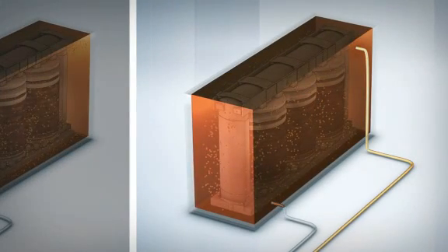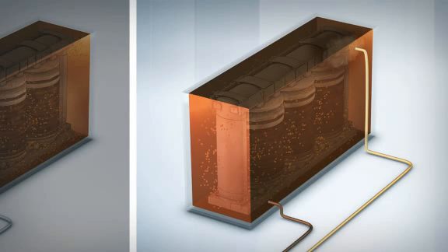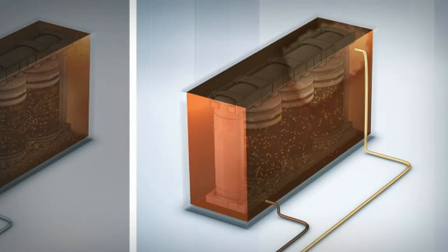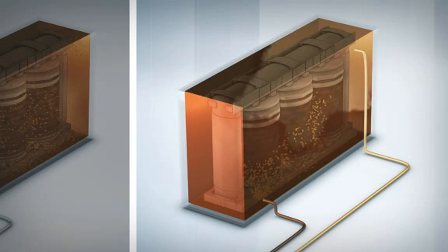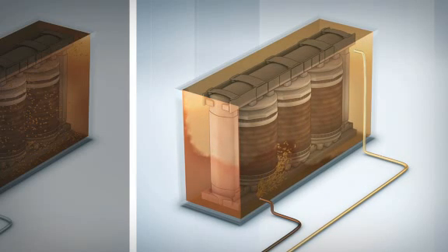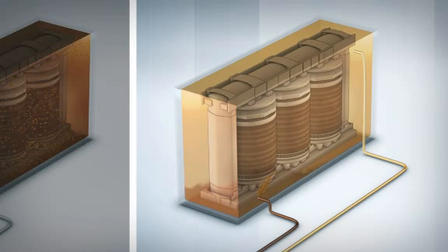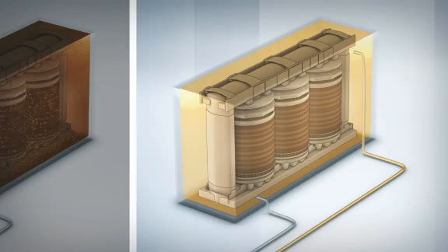Better results can be achieved by regenerating the oil during transformer operation. The transformer vibrations and the waste heat generated even serve to support the regeneration process. Continual regeneration also removes physical deposits. In terms of its characteristics, regenerated, inhibited, and degassed oil is the same as new oil. In some ways, it's even better. What's more, the process is more environment-friendly than a conventional oil change.